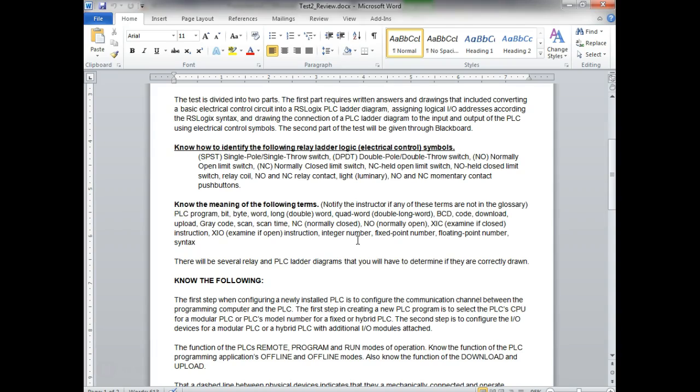But when you get into timers and counters, what do you think counters are? Input or output? They're output. So they'll go on the right. Timers will be output. They'll go on the right. So we'll learn that besides these OTE instructions that we're dealing with right now, when we get into counters and timers, those are output instructions and they'll go on the right. To control the timer, you can put things on the left, right? On the L1 side.